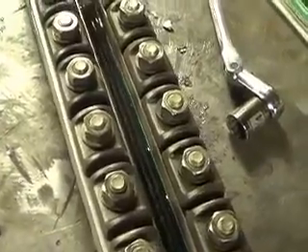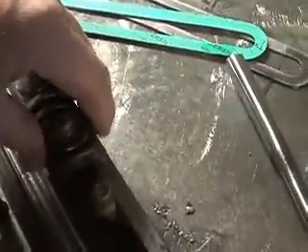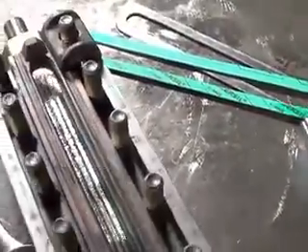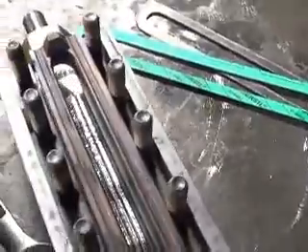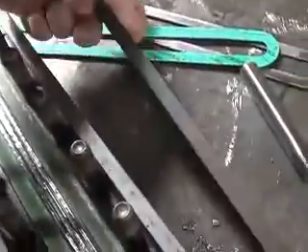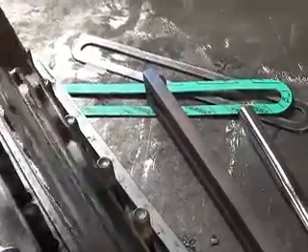Here's the side all done, and here's the side we're taking apart — does that look heavy duty enough for you? You've got these nuts, washers, and clamps, then you've got this bar that goes down. There's the old gasket — see the difference: this is the new one on the left and the old one on the right, all those little etch marks. That's why we've got to change it every year.